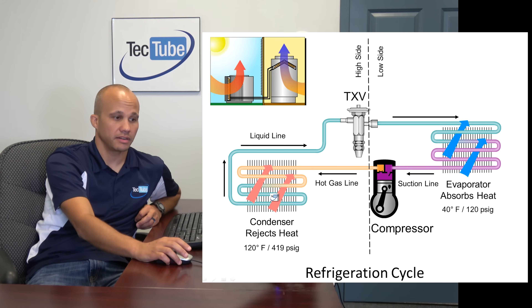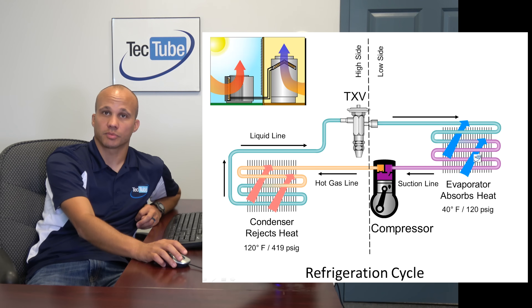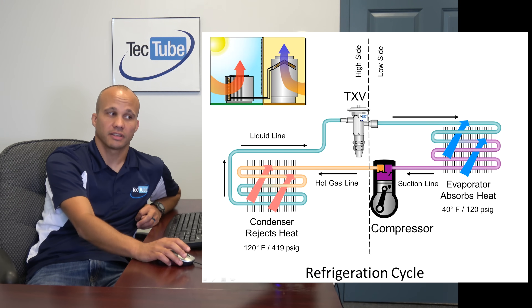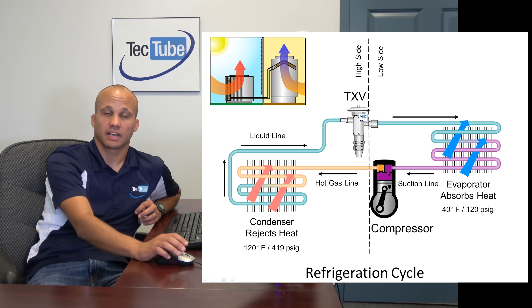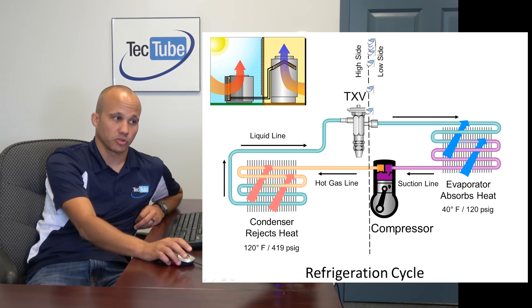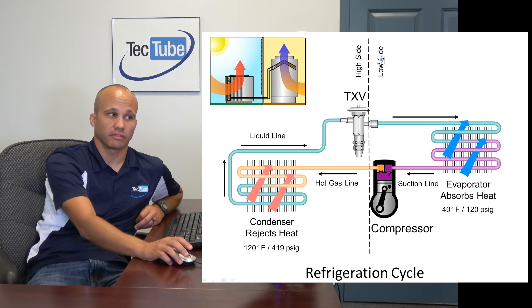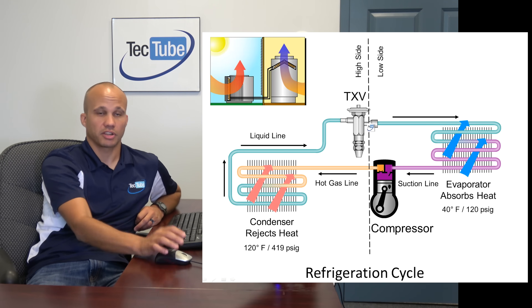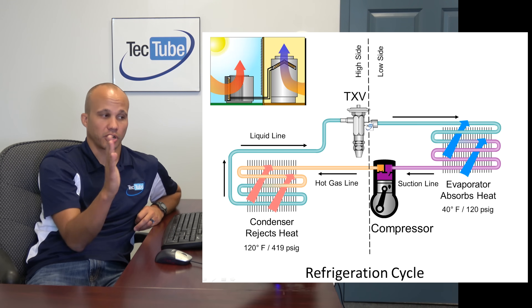The condenser coil rejects heat; the evaporator coil absorbs the heat. The compressor compresses the refrigerant, and expansion valves — or metering devices — allow that refrigerant to return to a lower pressure. On the left side of my dotted line I have high pressure, and on the right side I have low pressure. So the TXV and the compressor divide those pressure barriers.